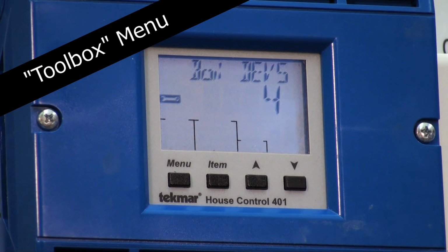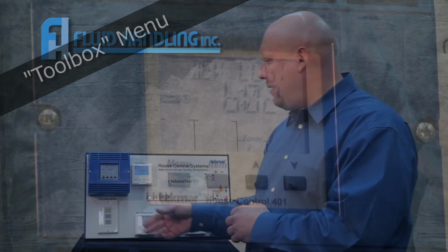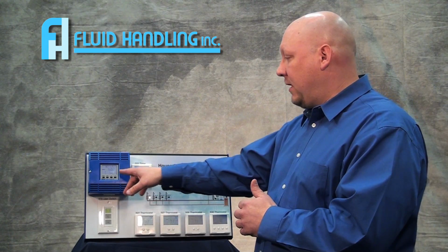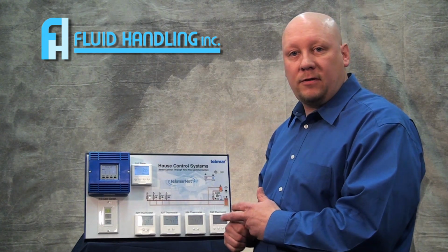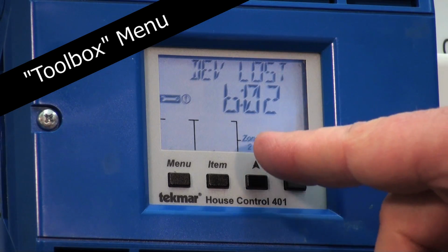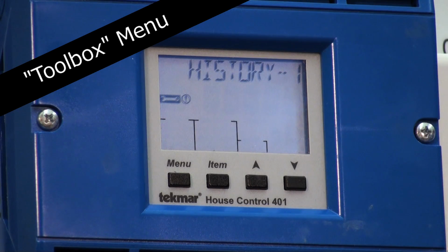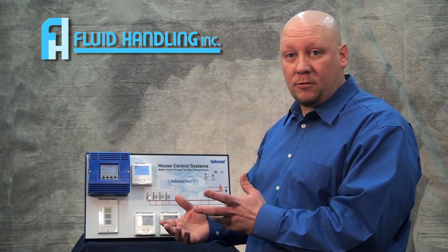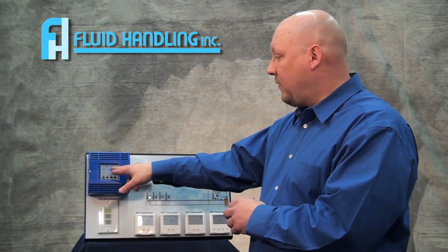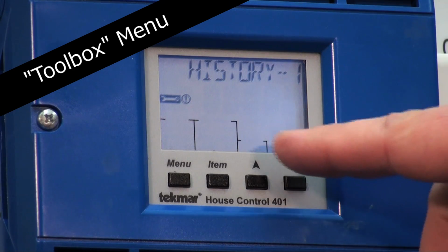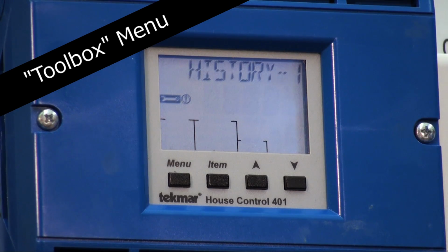And one way to know if it's reading, when you look at the thermostats, you see 2 arrows going in different directions. That means it's communicating with our control. And you've got history. It's showing me that I've had some devices that were lost and what device it is, which happens to correspond with the appropriate zone too. So if you disconnect the thermostat, a wire gets broke, a wire pops off, a device might get lost, but it's going to tell you which device it is and you need to figure out what's going on.